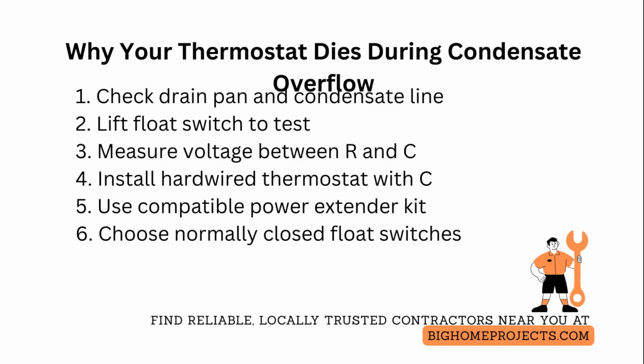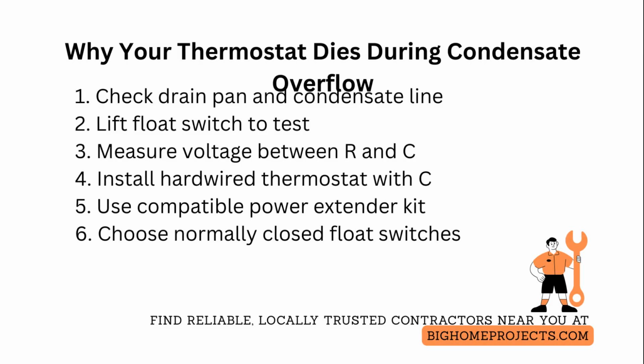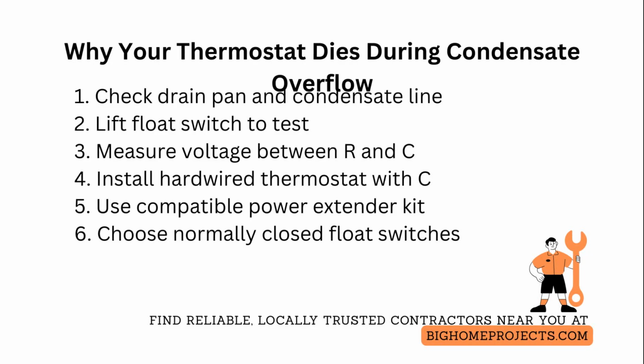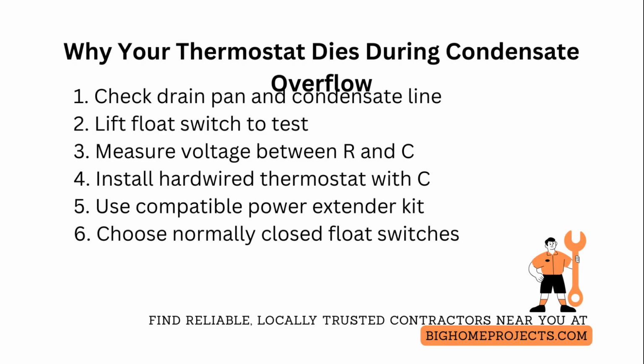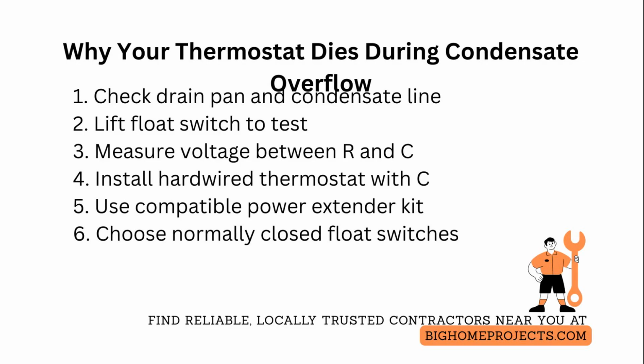Third, if the float switch does interrupt the R feed, retrofit a hardwired thermostat powered from both R and C instead of relying on battery-only models, or install a compatible thermostat designed to tolerate open safety circuits, and that can detect calling behavior without constant R power. Fourth, if running a new C wire is difficult, consider using a power extender kit that uses existing wires to recreate a stable common reference, but only use kits proven compatible with float switch circuits and follow manufacturer wiring diagrams.